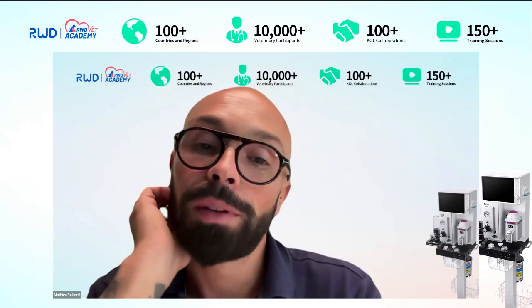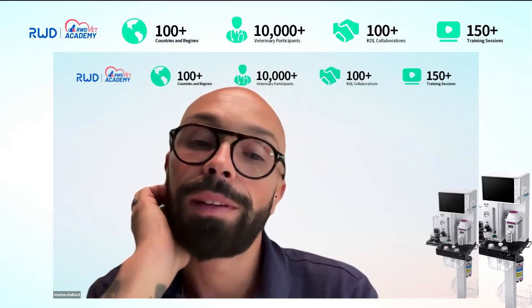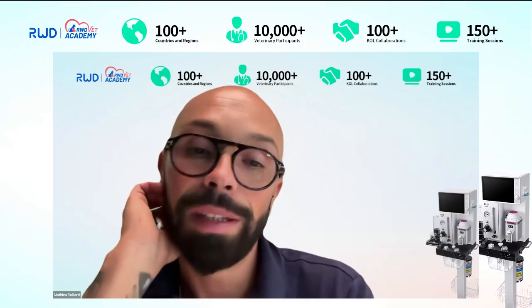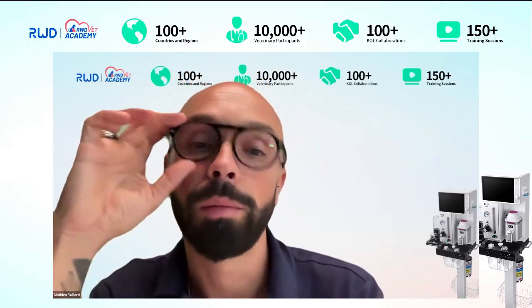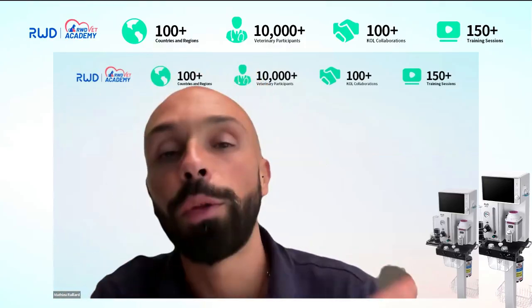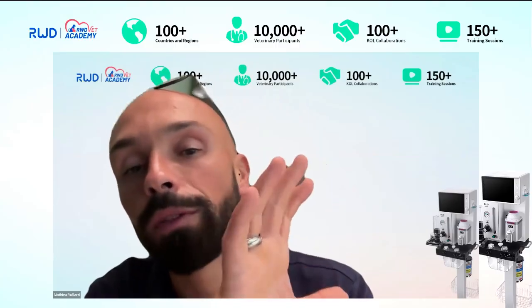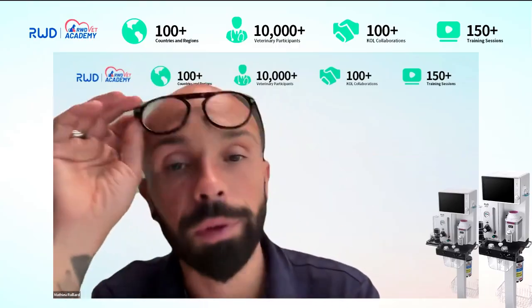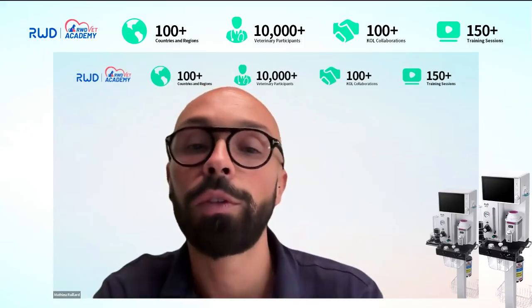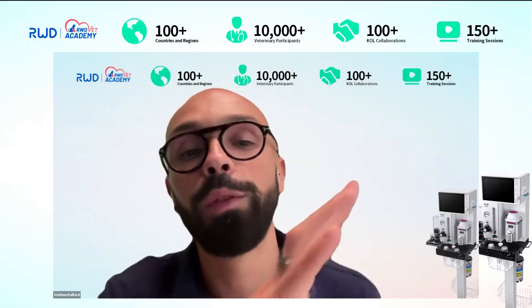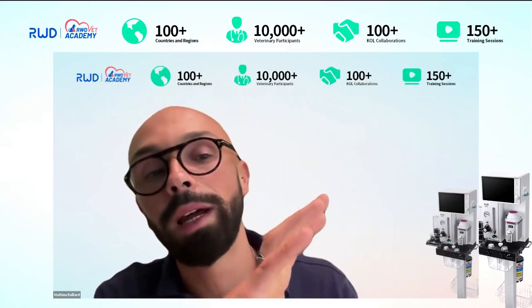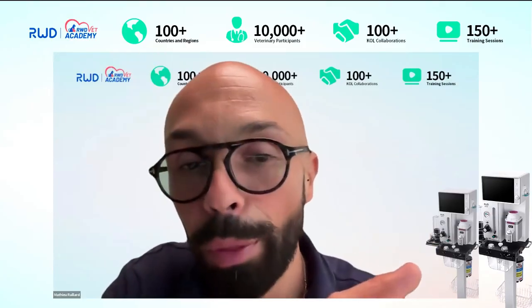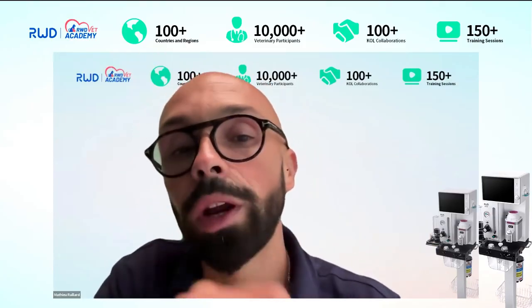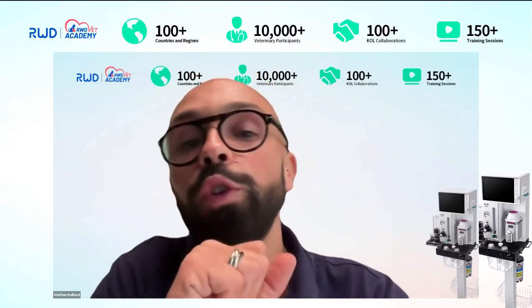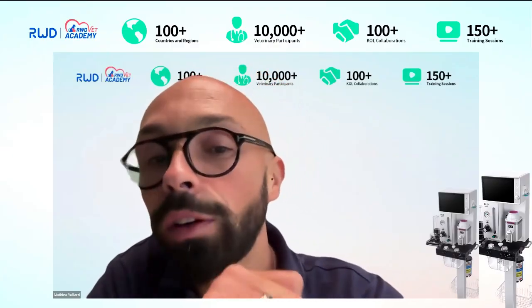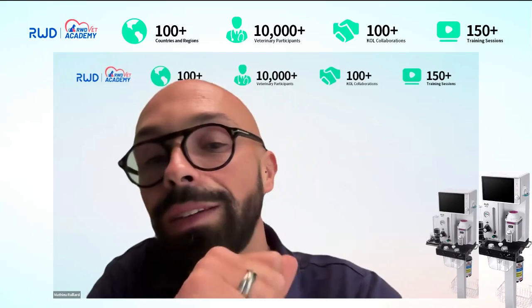When you use synchronized intermittent ventilation, you rely on the ventilator recognizing an inspiratory effort from your animal. So your trigger, on synchronized intermittent mandatory ventilation, is this: you have a controlled breath that happens at a time you set, but you also have breaths in which the ventilator will help the animal that tries to take a breath. So your trigger becomes the animal. I use synchronized intermittent mandatory ventilation in ICU ventilators.